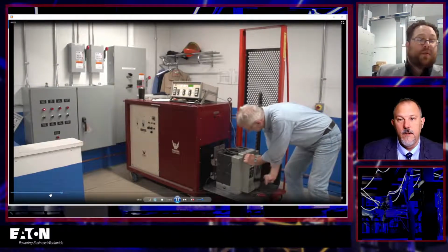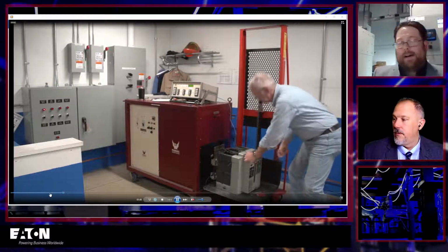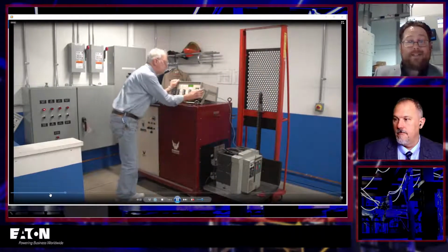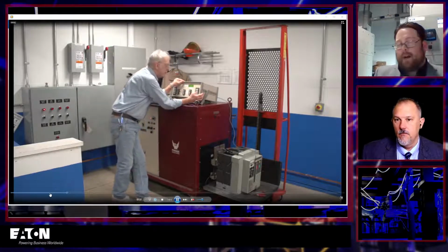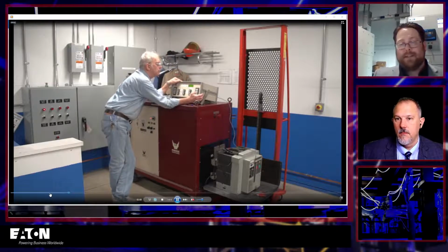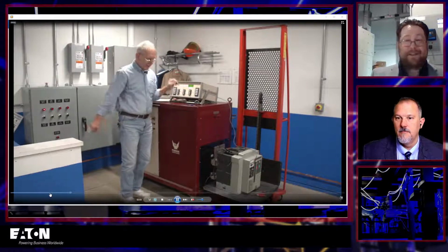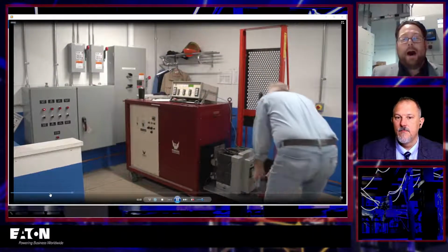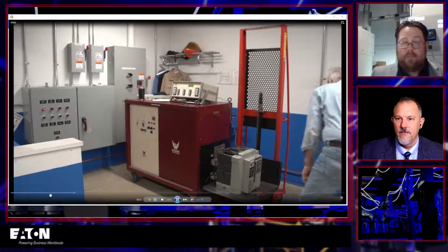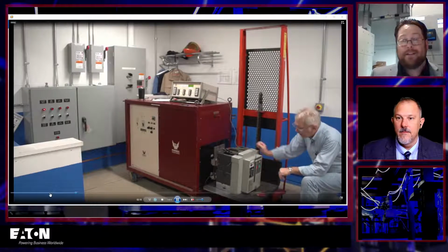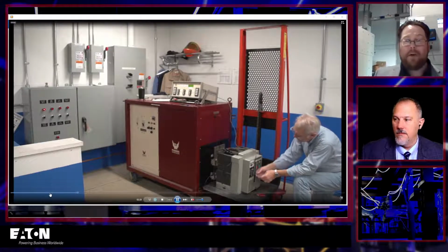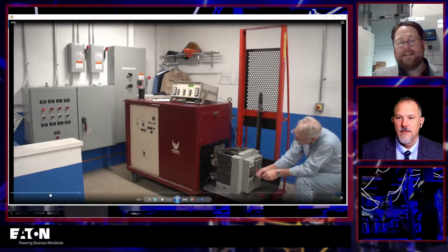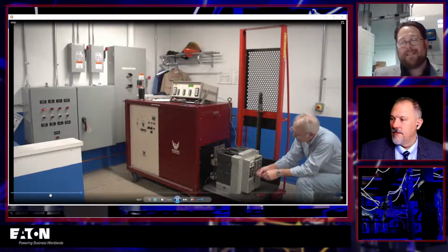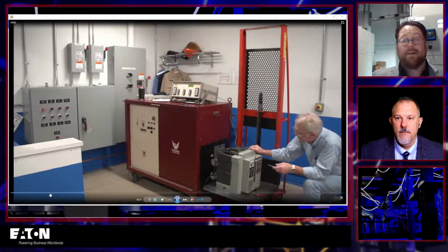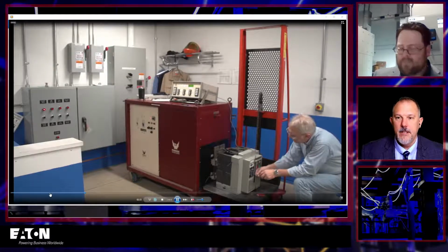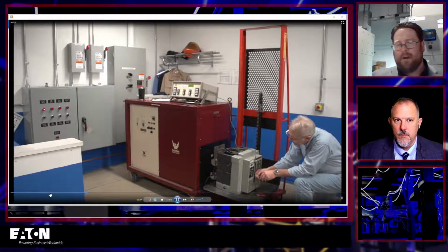What gives, Michael? So the big thing about a primary injection test set is that while you are pushing out that high current, there's actually no voltage driving that current. A lot of our customers are concerned about primary injection because when you look at breaker manuals and read the instructions and the standards, breakers are only made to interrupt a few faults at the high currents before they need to be serviced, because you're going to burn off contact material and all that kind of stuff happens behind the scenes. In a primary injection test set, you're pushing the current, but there's actually no voltage, so the power going through the breaker is not that great. That's generally why you're not seeing the use of gloves and all the shock protection.